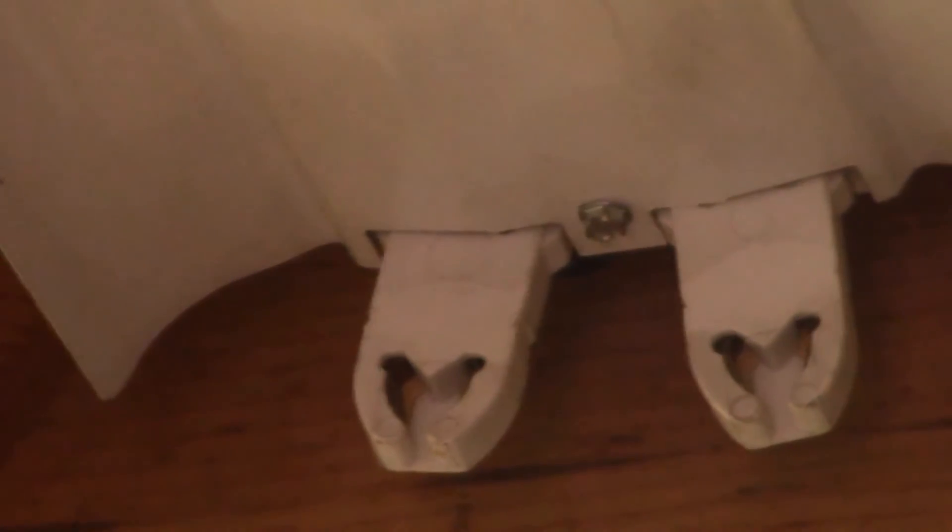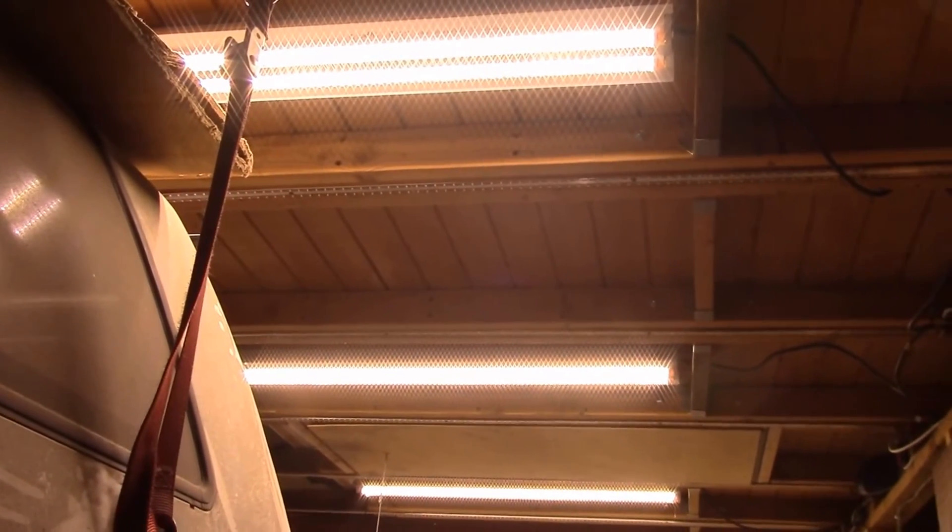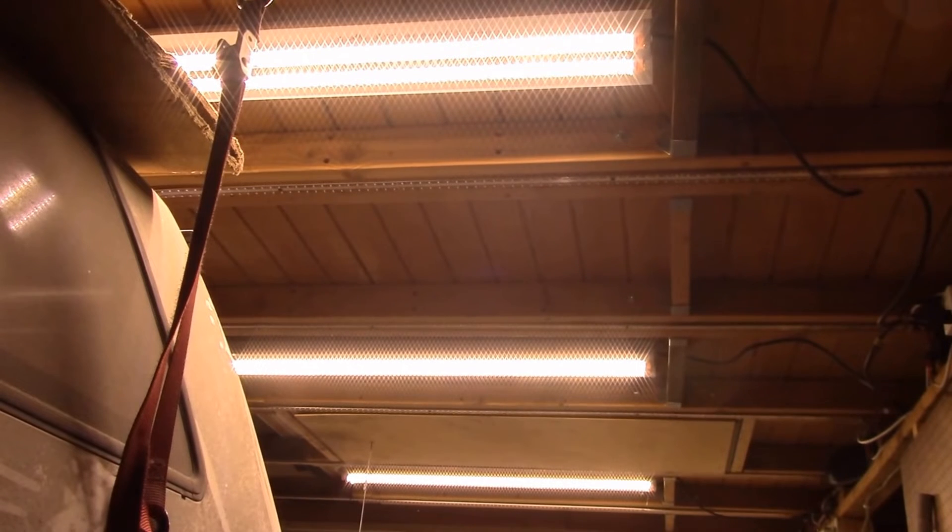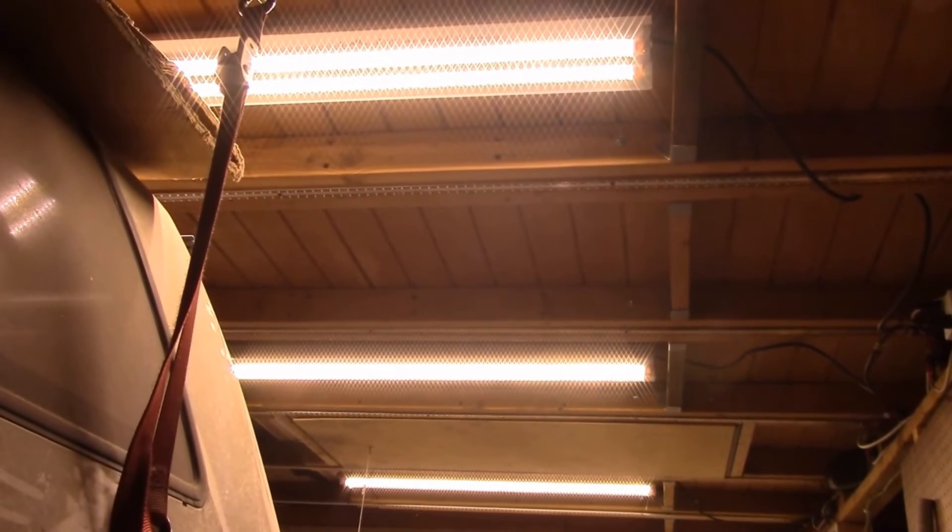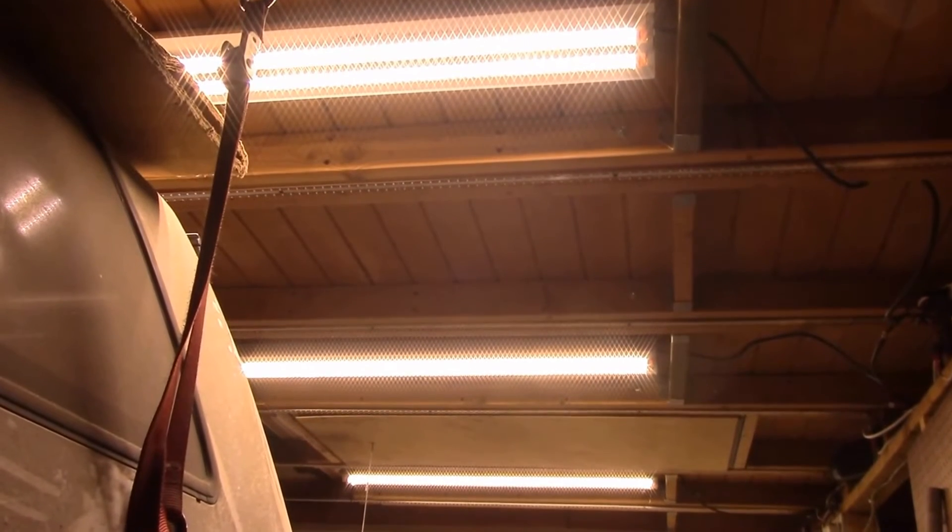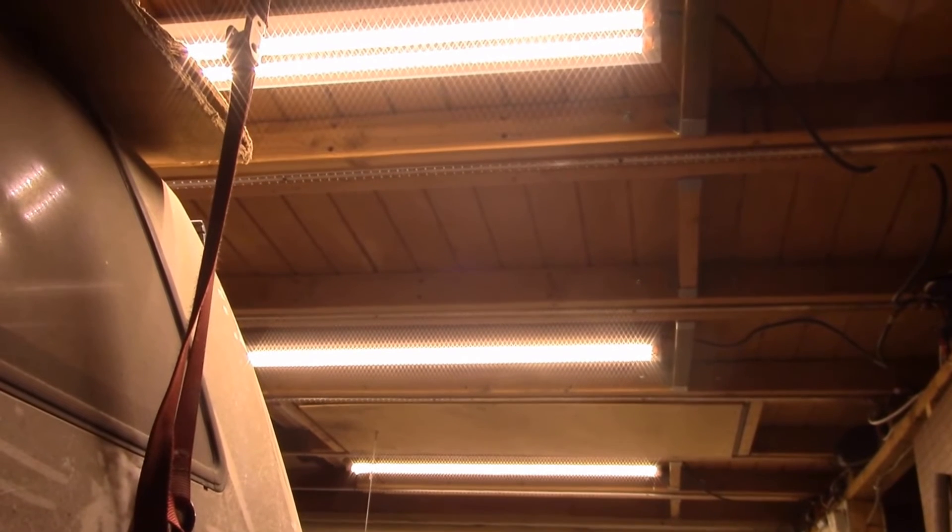So I'll show you what it looks like when it's done. Well, there we go! Three T12 fixtures from the 1980s converted to T8 LED tubes with no ballasts. And I've gone from 240 watts down to 120 watts of light right there. And I'll just show you what my solar looks like.